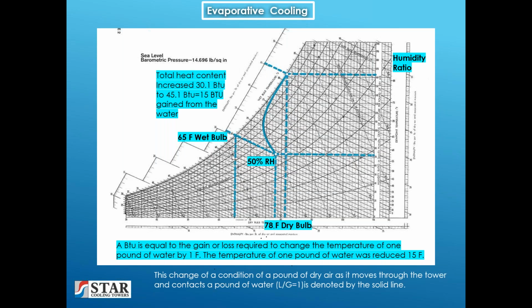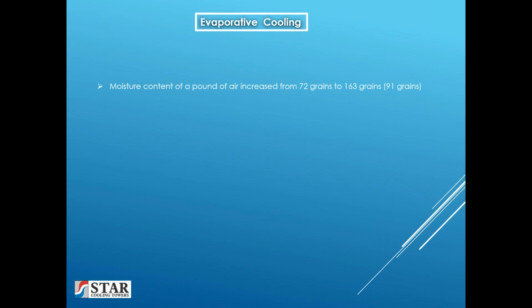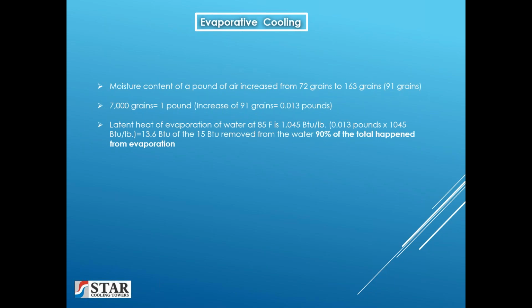If we look to the right at the humidity ratio, we find that we started at 72 grains of moisture and ended at 163 grains of moisture. So this moisture content of a pound of air increased from 72 grains to 163 grains, which is 91 grains of moisture. 7,000 grains equals 1 pound, so an increase of 91 grains is 0.013 pounds. The latent heat of evaporation of water at 85 degrees Fahrenheit is 1,045 BTUs per pound. So 13.6 BTUs of the 15 BTUs removed from the water, 90% of that total, happened from evaporation.